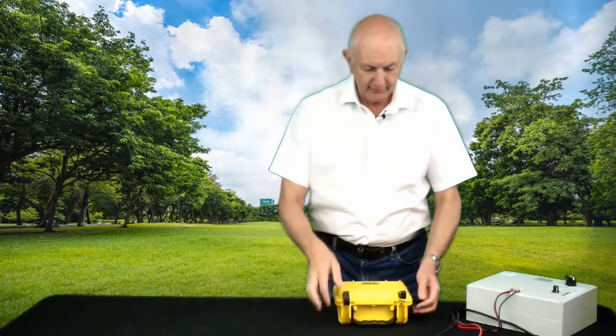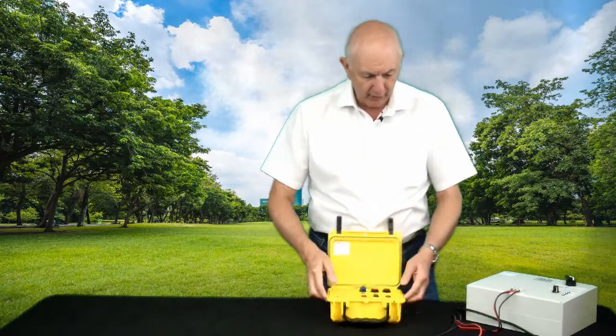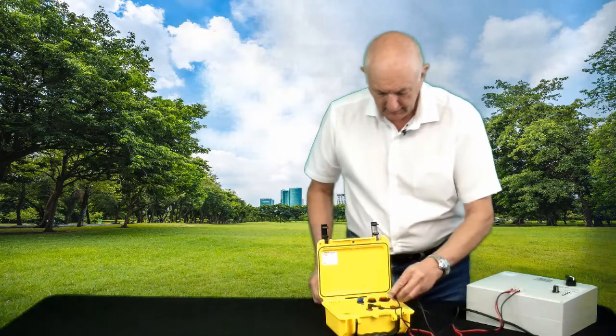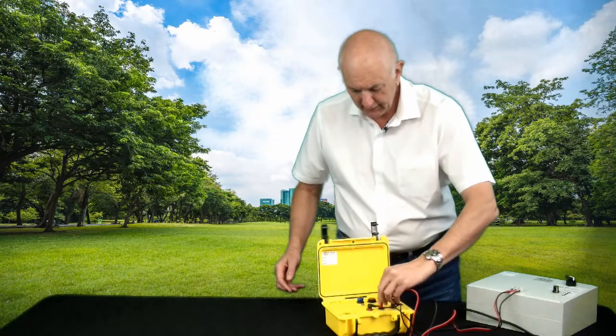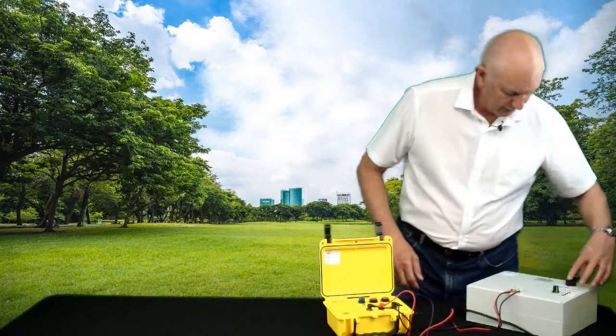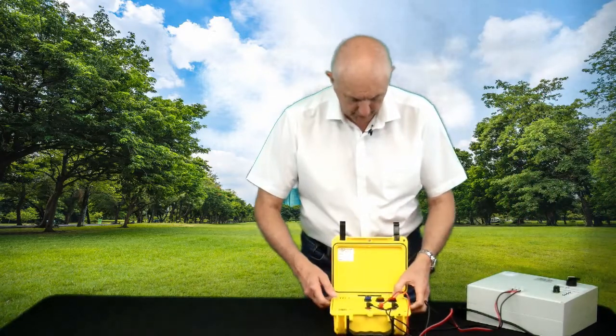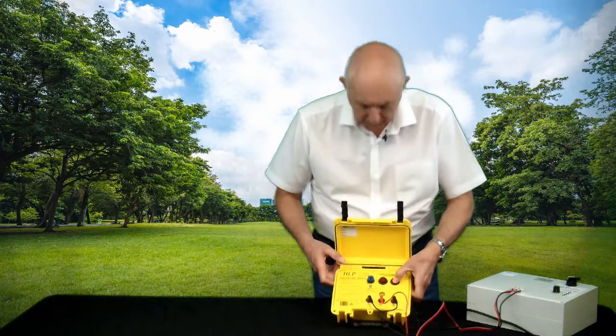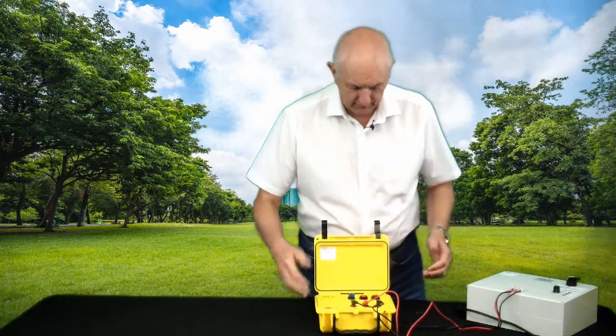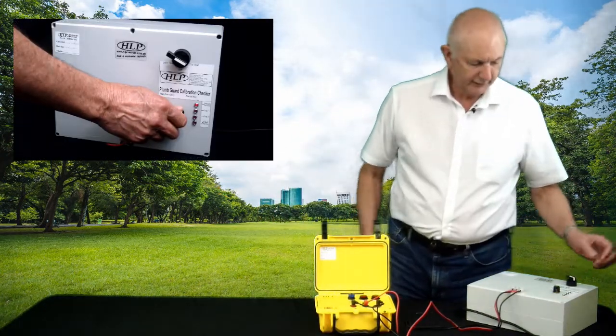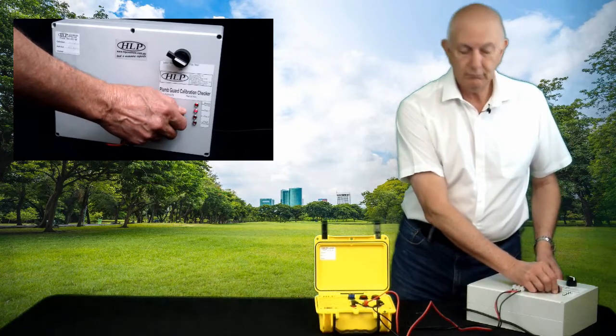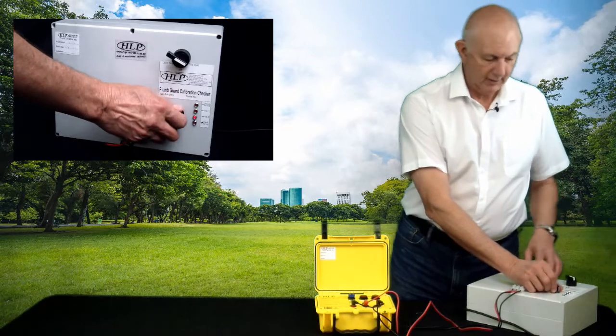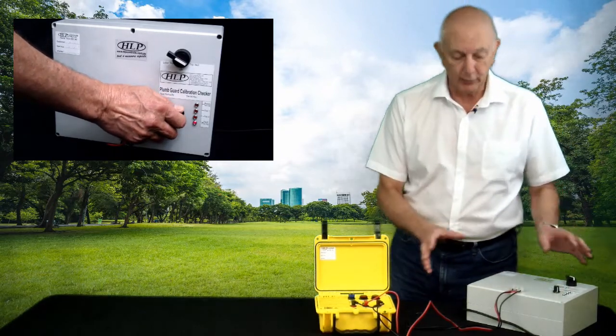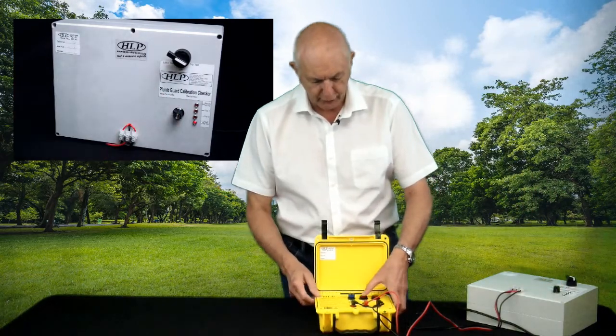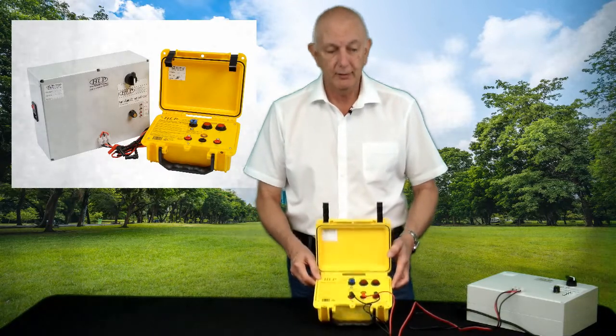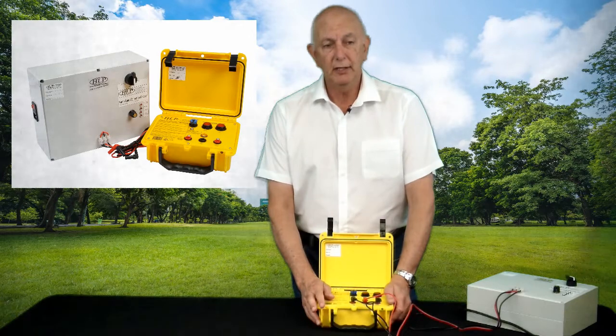So with that unit plugged in, just to clarify again, we turn the power on. Plug the kit in to the 3 sockets. We select the lead test and do the self-check on the Plumb Guard. So the self-check works. The Plumb Guard's now running. So we select trip test, position 1, no trip, position 2, trip. And if it didn't trip there and we went to position 3 and it tripped, that's also okay. So either of those 3 positions, as long as you get a trip, that certifies that the Plumb Guard's working and it's the right level. So it's as simple as that. So you can literally do one of those in less than a minute.